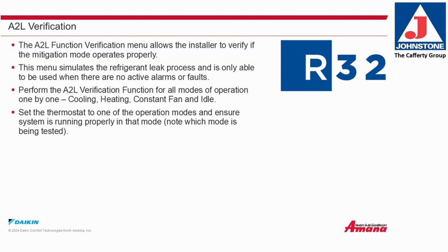A2L verification. The A2L verification menu allows the installer to verify if the mitigation mode operates properly. The menu simulates the refrigerant leak process and is only able to be used when there are no active alarms or faults. Perform the A2L verification function for all modes of operation one by one: cooling, heating, constant fan, and idle. Set the thermostat to one of the operation modes and ensure the system is running properly in that mode. Note which mode is being tested.